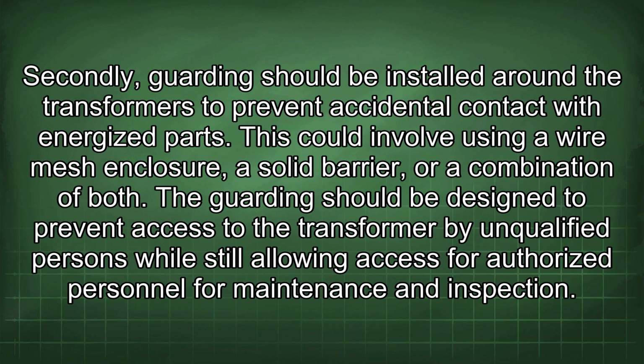equipment. Secondly, guarding should be installed around the transformers to prevent accidental contact with energized parts. This could involve using a wire mesh enclosure, a solid barrier, or a combination of both. The guarding should be designed to prevent access to the transformer by unqualified persons while still allowing access for authorized personnel for maintenance and inspection.